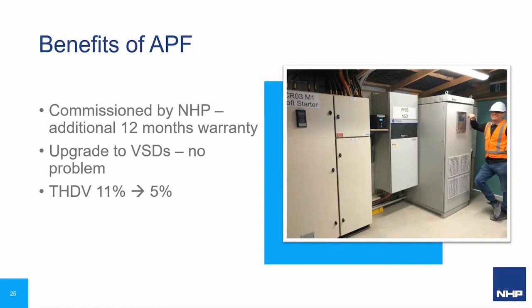Now, one of the key considerations in the application of the APF was this low reliability of the 11 kV supply. So should the 11 kV feeder go offline, the entire site needs to run from generator power. So without the APF, the harmonic voltage distortion would have been far, far too great for the existing capacitor-based power factor correction system to tolerate, and would inevitably have suffered damage and gone offline, resulting in the entire plant becoming inoperable altogether. Mm-hmm. Yeah. Definitely don't want that. So. Indeed.